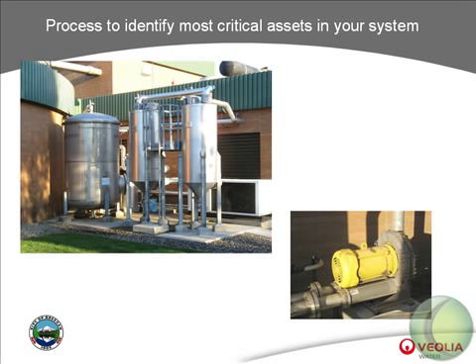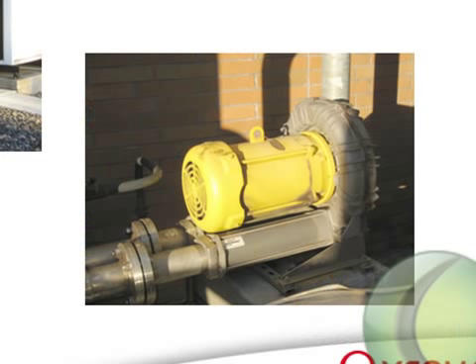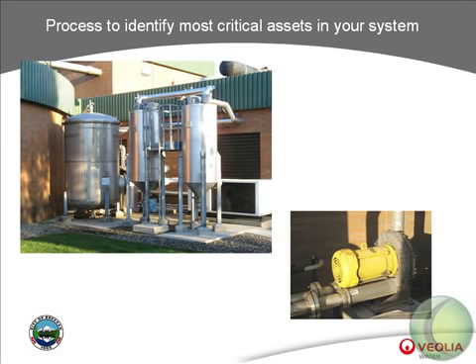The gas conditioning system achieved a high ranking because of its collateral damage potential and a single point of failure, the system blower. The result of the review was to investigate the blower replacement lead time, which was found to be 12 to 16 weeks, and to get one of these into the critical spares inventory.